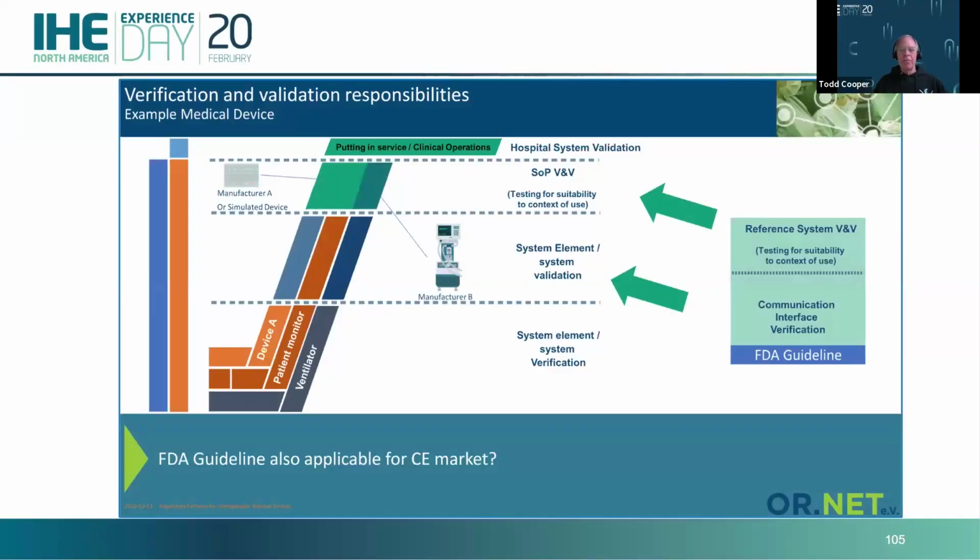And this is just another example of how a specific device A, I think that was an app, a patient monitor and a ventilator, work together to provide specific clinical system functions. But notice this, the FDA right now, we're very actively talking to them about recognition of SD-PI. They've recognized the core standards for this device interoperability, the SDC standards, service-oriented device connectivity, but they recognize that the products that are submitted to them will have testing. We are calling it regulatory submission-ready test reports that we anticipate coming out of IHE connectathons and especially conformity assessment. They want to recognize SD-PI for this capability. Very active discussions, and we're looking forward to hopefully giving them a tour. They're very interested in seeing what's coming up in the interoperability showcase in a few weeks.